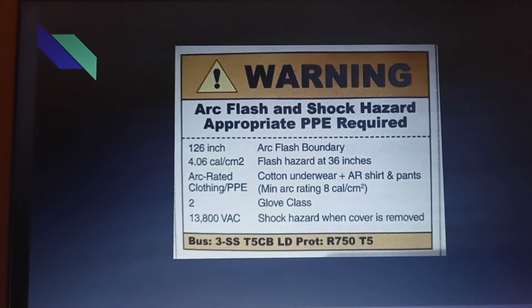You got arc flash and shock hazard, appropriate PPE required. You got 126-inch arc flash boundary. You've got 4.06 cal/cm² flash hazard at 36 inches. So your arc rated clothing needs to be cotton underwear and AR shirt and pants, minimum arc rating of 8 cal/cm². And then class 2 gloves, and then 13,800 VAC shock hazard when cover is removed.